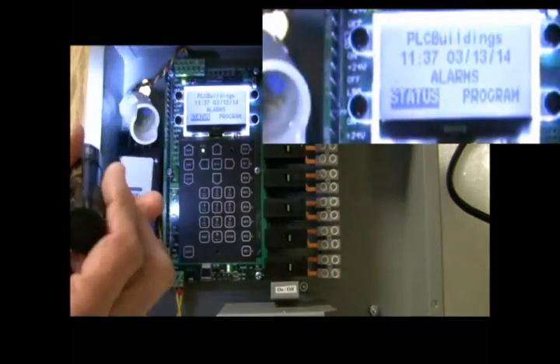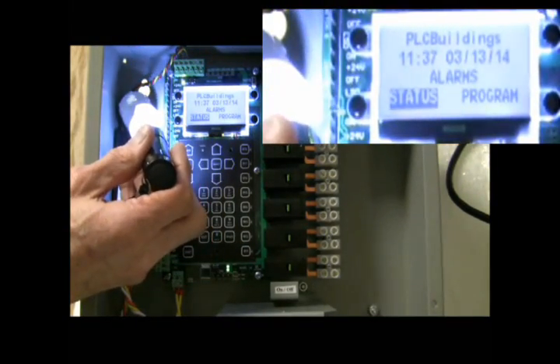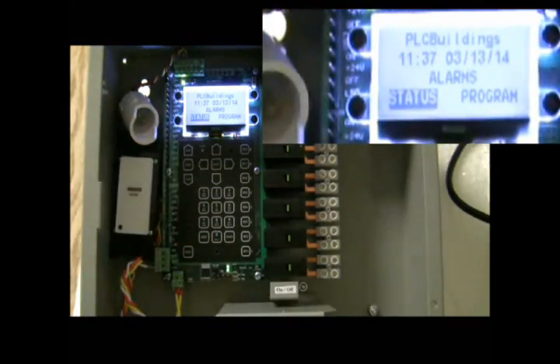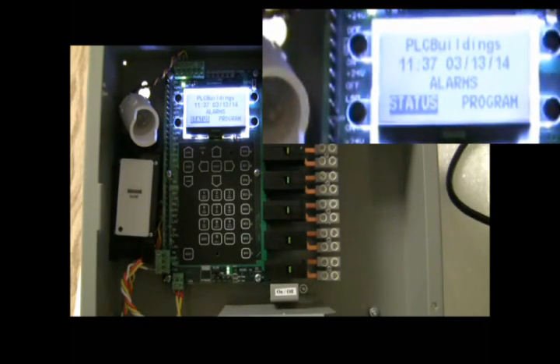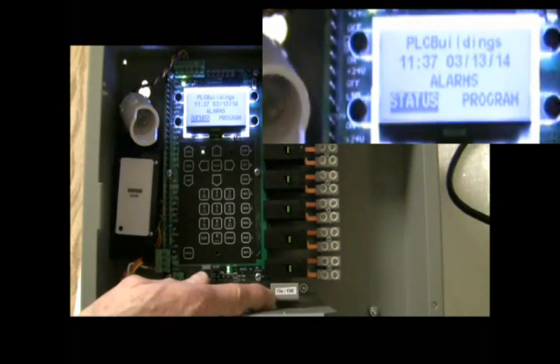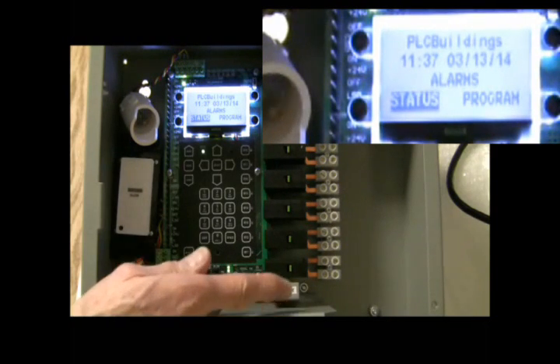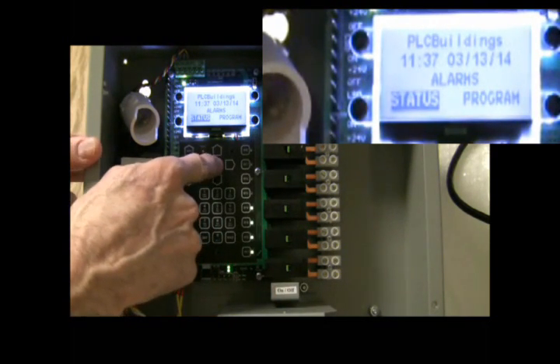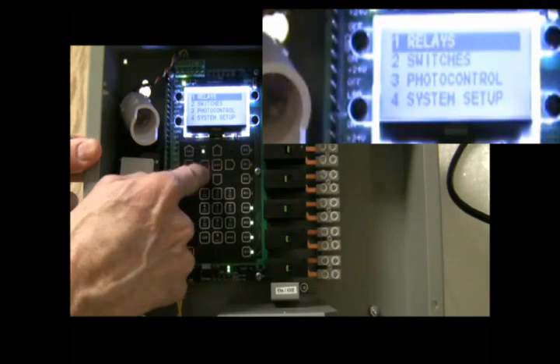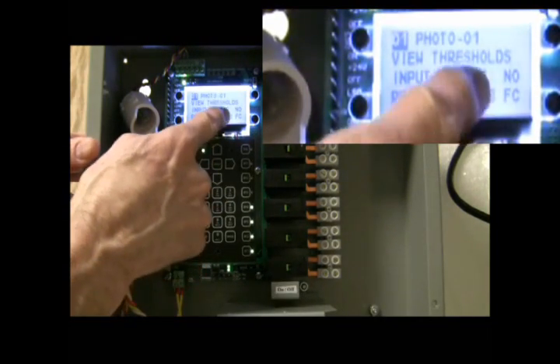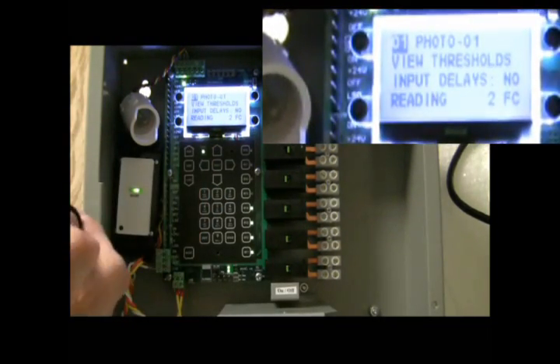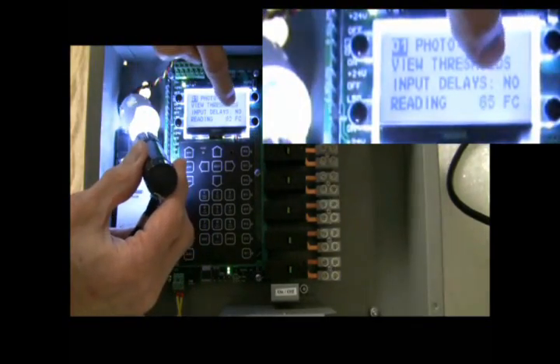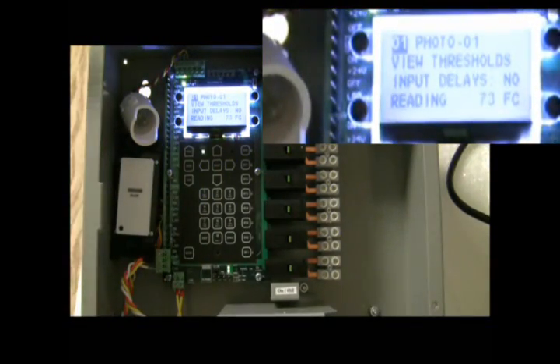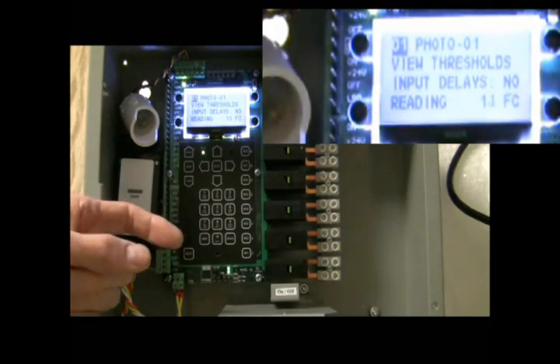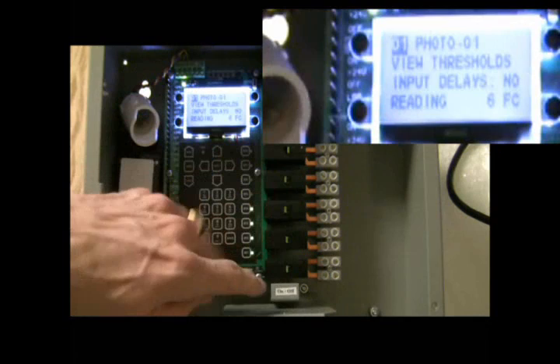Because we want to see the sensor activate those relays. The relays will go off when there's lots of light, and as the signal decays, they will come back on when it goes down below the threshold. To see what that threshold is, you can look at it with status, photo control, and you'll be able to see the foot candles. Shining a light, foot candle goes up right away. It'll decay back down. The defaults for this are like 10 foot candles when it switches off. So it's nighttime now. They've turned on.